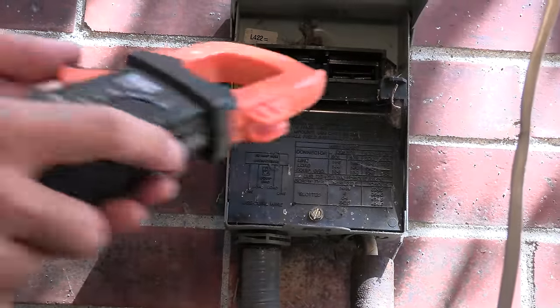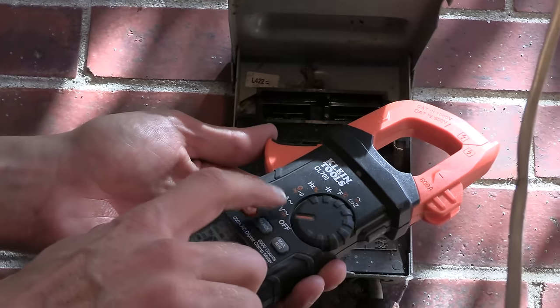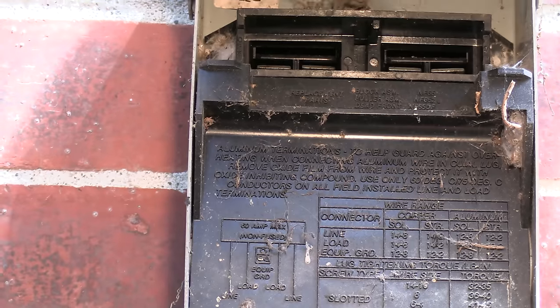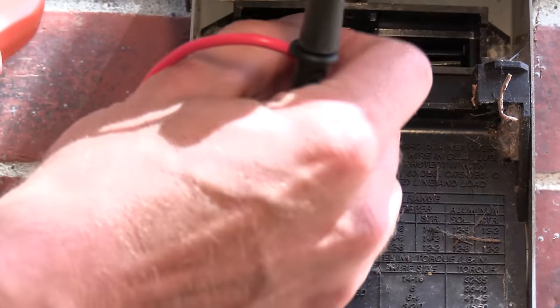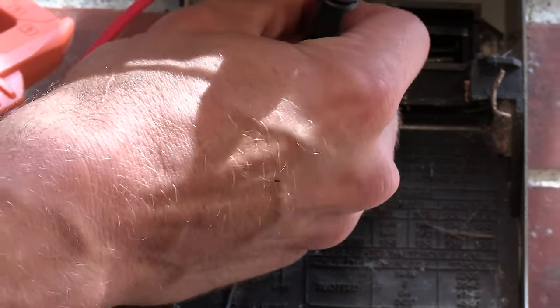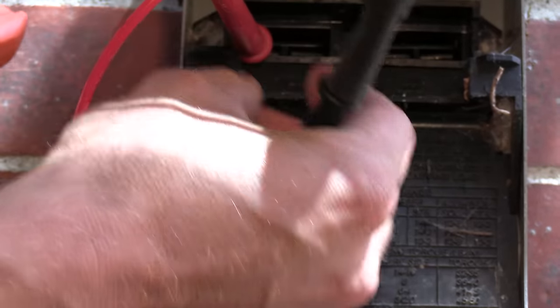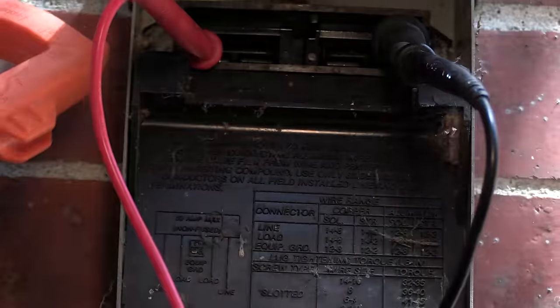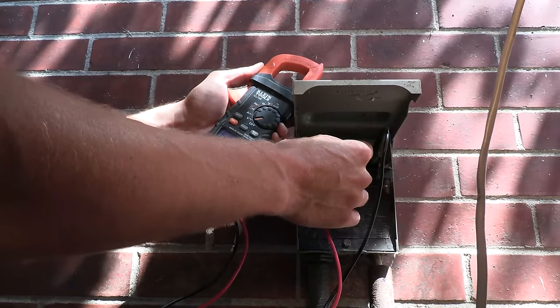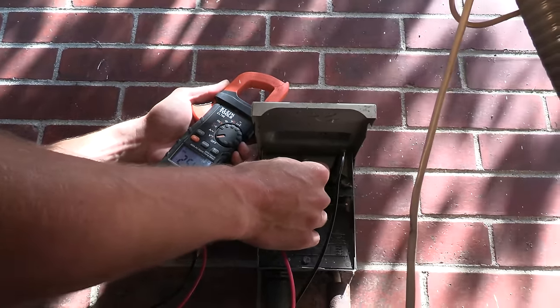If I don't have the alligator plugs, but I've got a standard multimeter, I can also use that. I'm going to put it on volts AC. Then I'm going to take my probes, and I can stick them in there. Either way, black on right, or red on left, or vice versa, is going to work just fine. And I'm going to confirm. I will say the alligator clips are tough to fit in there. And there I have it, 255 volts AC. Now I've got a clear read whether my air conditioner power is on or off, and I can go identify the circuit.